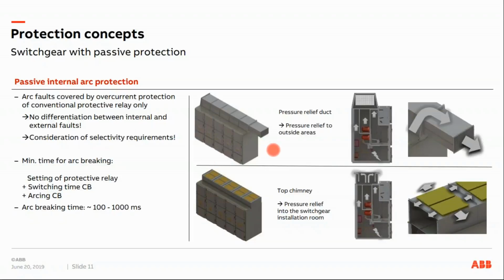However, for this kind of conventional protection approach, the fault detection is done by a standard relay, and the clearing of the arc fault current itself is done by the upstream circuit breaker. So usually we are talking here about a minimum time for the arc breaking of 100 to 1000 milliseconds, which depends on the setting of the protective relays, the switching time for the circuit breakers plus the arcing time for circuit breakers. So that might be already too late for your system to overcome such a harsh fault.